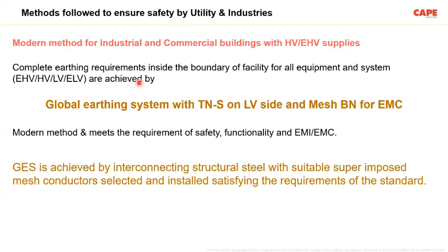The touch voltage we got, the result of the test, was less than 2.1 volt, in comparison to the tolerable limit of probably 600 or 800 volt. That is the limit, but the actual touch voltage was less than 2.1 volt. A global earthing system is an earthing system achieved by interconnecting every exposed and extraneous conductive part in a building. You make a maximum interconnection. As a result, touch and step voltages do not exist in the building.